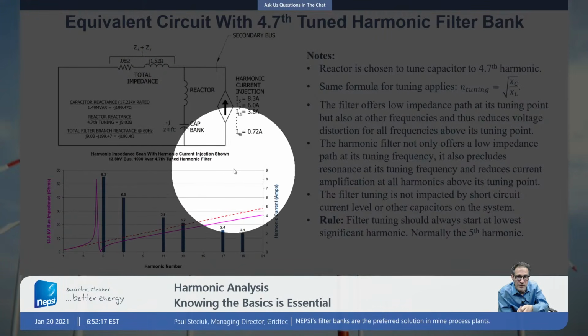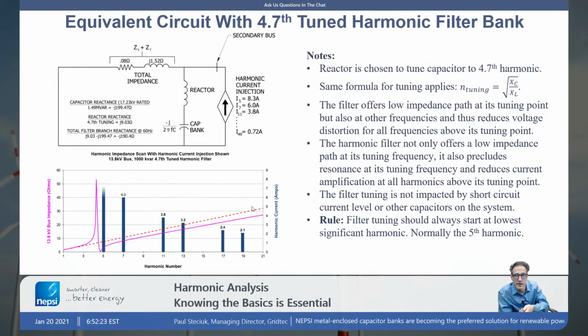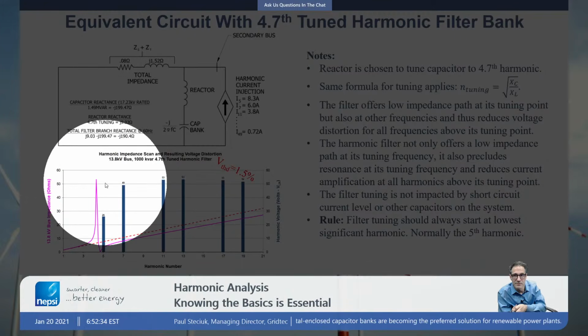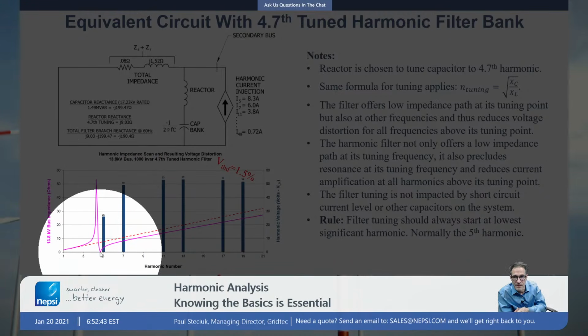plant. So here we're taking the current injection values, those values there, we're multiplying it times the impedance along this whole curve, and we come up with a bar chart for voltage distortion. And here you can see the voltage distortion has dropped. The other thing to note is that we pushed the resonant point down below the tuning point. Another benefit of adding capacitors as harmonic filters is that we dictate this point right here. That point is dictated by the tuning point of the filter, and the resonance is always beneath or lower than that tuning point. And it's one of the reasons why filters are always tuned to the lowest frequency first.